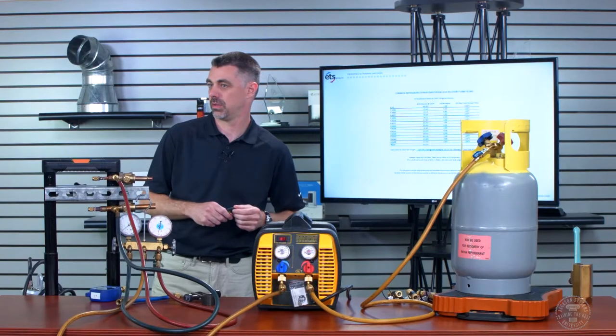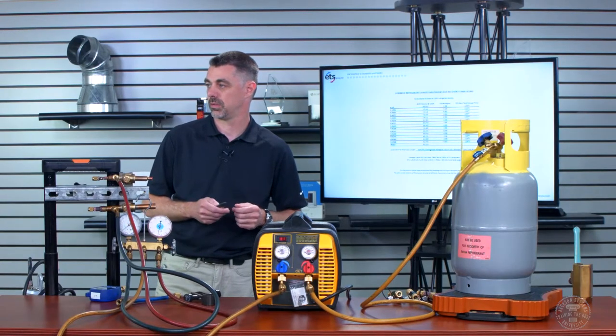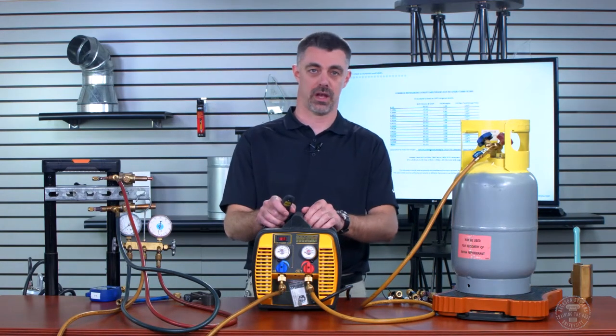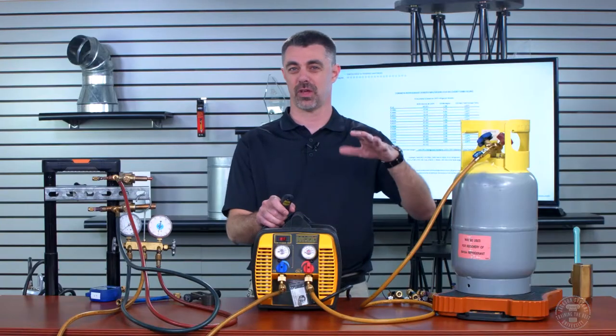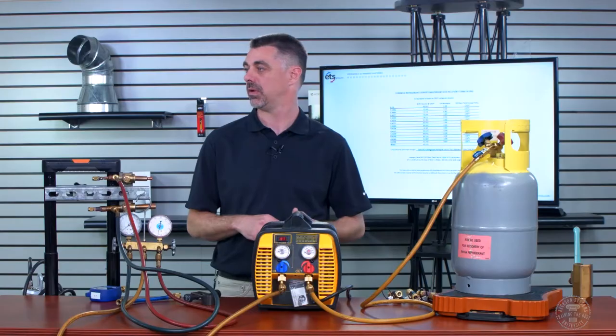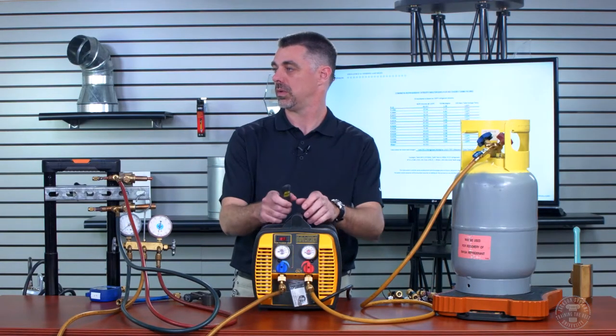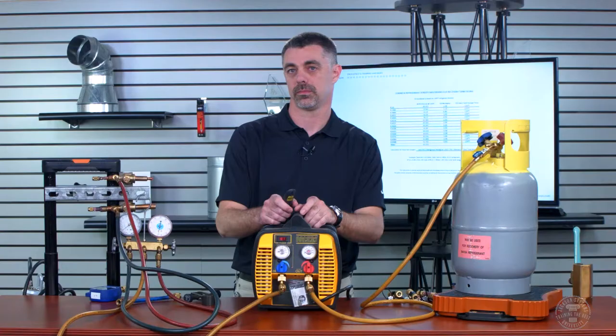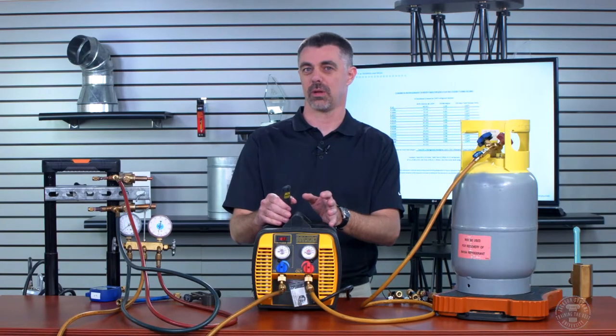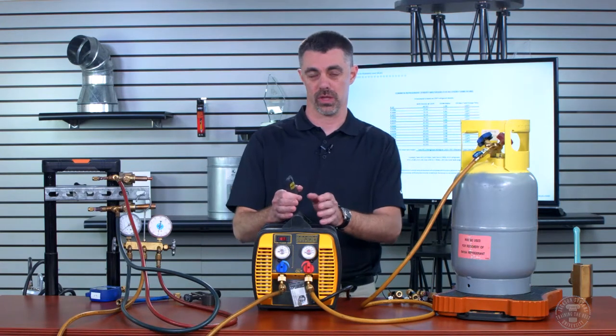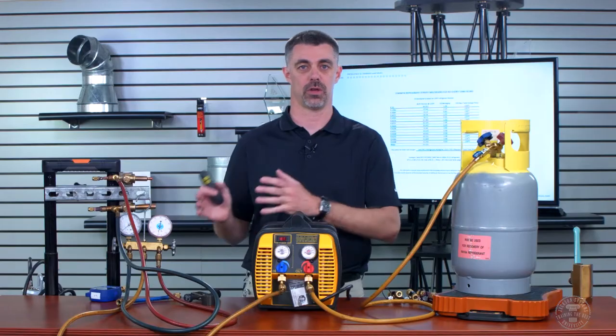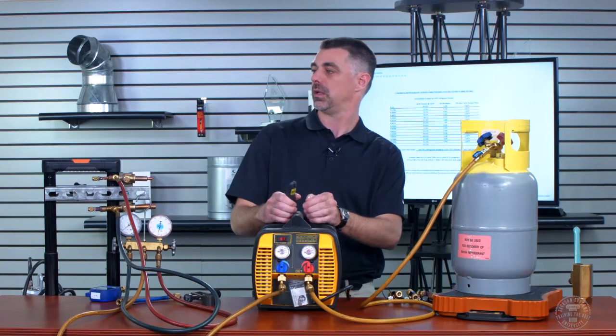A question: can the same-size tanks have different tare weights? They can vary somewhat — sometimes about half a pound difference — so always do the calculations for the specific tank you have. On evacuation times: it doesn't matter as much what refrigerant you're using; it matters what state you're moving it in. Liquid has greater density and moves faster, so keep everything as liquid as possible.